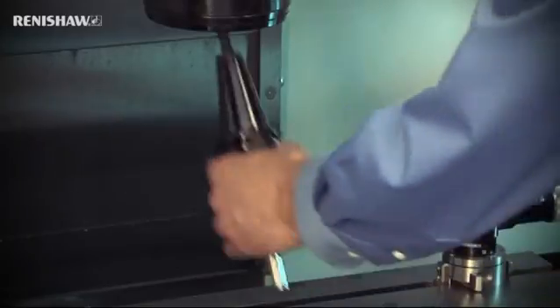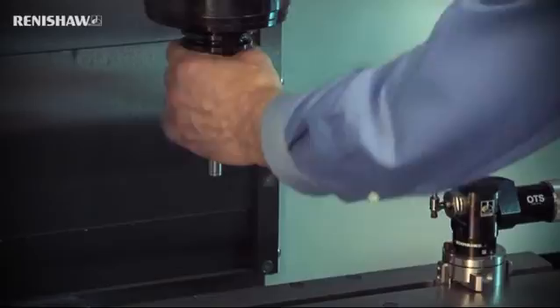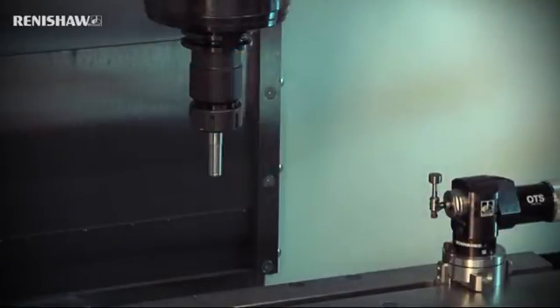Note that when mounting the tool cup to the spindle in this manner, it is important to ensure that the spindle is locked and cannot rotate. Any rotation of the spindle will result in a test error.